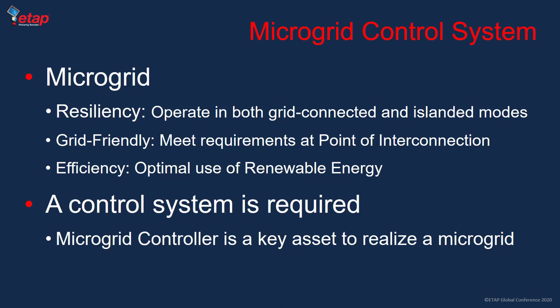Another aspect of the microgrid is efficiency. A microgrid control system allows optimal utilization of renewable energy resources. By having energy storage, you can do peak shaving and price arbitrage, making the microgrid more efficient and improving the usage of renewables. In order to achieve these three attributes — resiliency, grid-friendly operation, and efficiency — a control system is required.